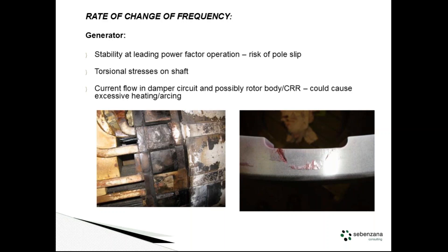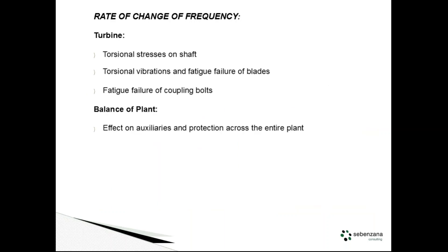If the machine goes out of synchronicity, you get like a squirrel cage of an induction rotor — it uses currents in the damper circuit to speed it up or slow it down. While you're rapidly changing frequency, you're inducing currents in this damper circuit. If it's not designed for it, you're going to have problems. This is a case where a damper circuit actually melted with severe arc damage onto a core retaining ring, which had to be thrown away. On the turbine, again, you've got torsional stresses, vibrations, and fatigue failure of blades in the long term.